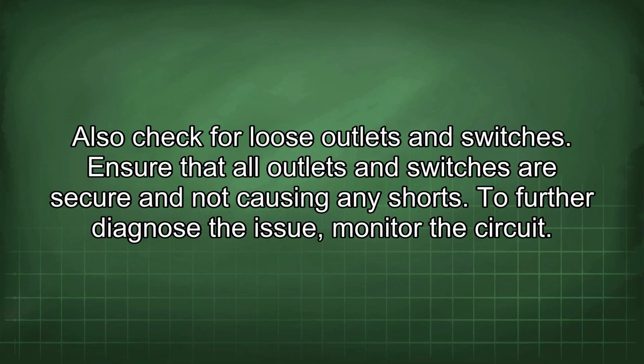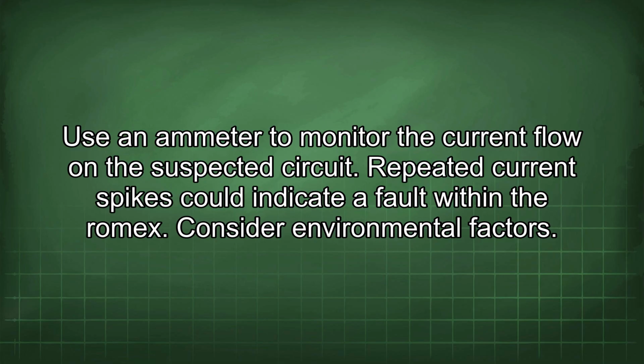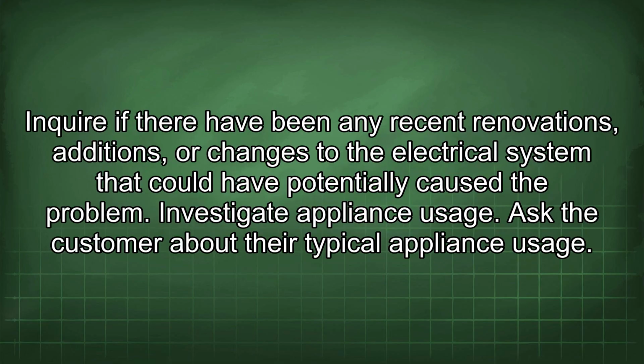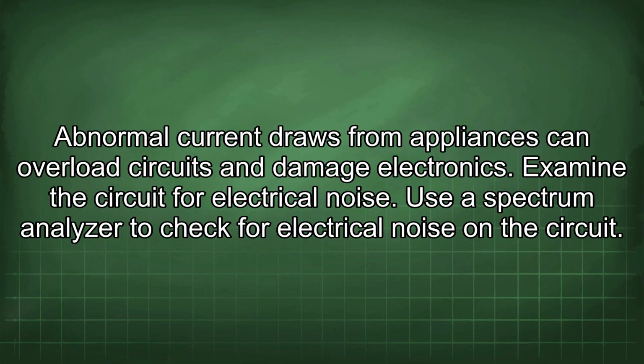To further diagnose the issue, monitor the circuit. Use an ammeter to monitor the current flow on the suspected circuit. Repeated current spikes could indicate a fault within the Romex. Consider environmental factors. Inquire if there have been any recent renovations, additions, or changes to the electrical system that could have potentially caused the problem. Investigate appliance usage. Ask the customer about their typical appliance usage. Abnormal current draws from appliances can overload circuits and damage electronics.